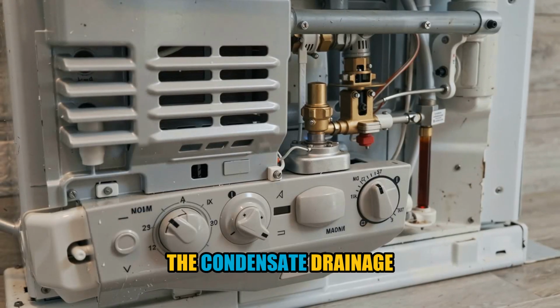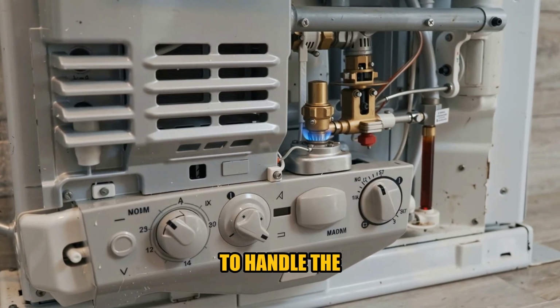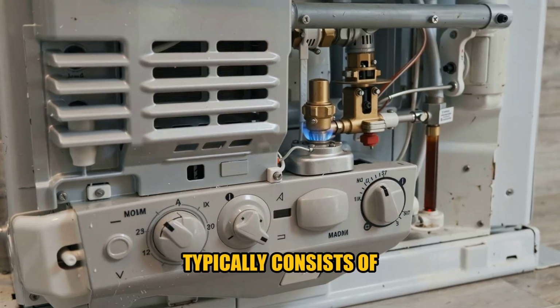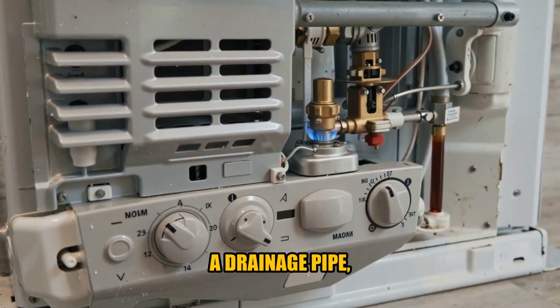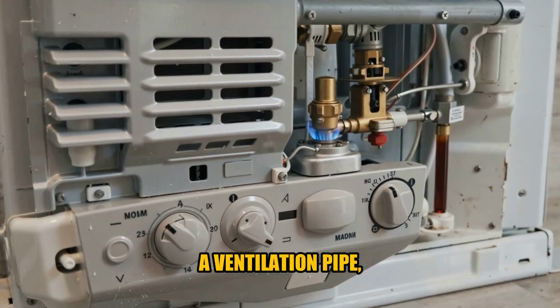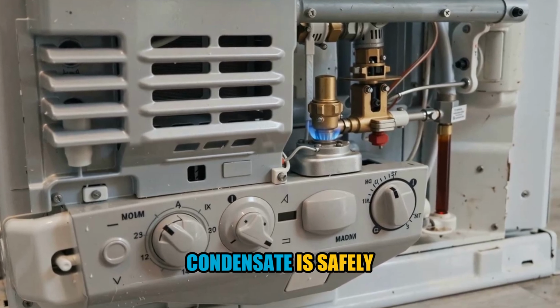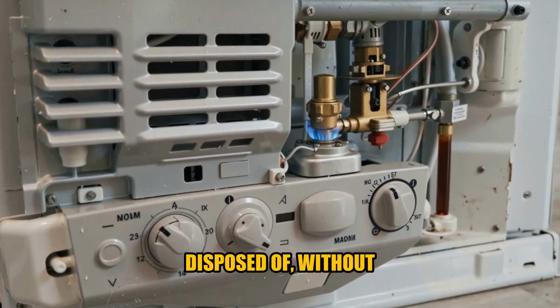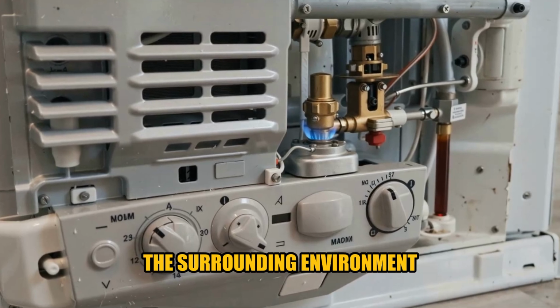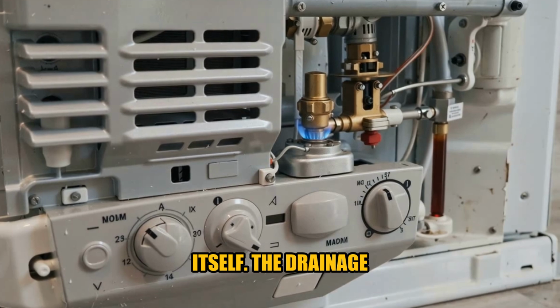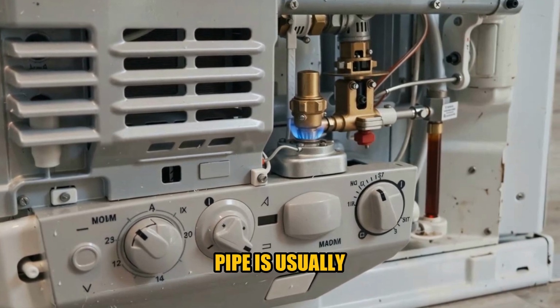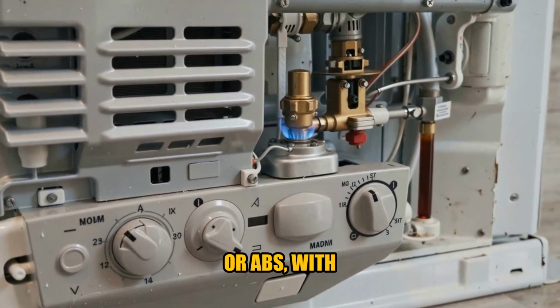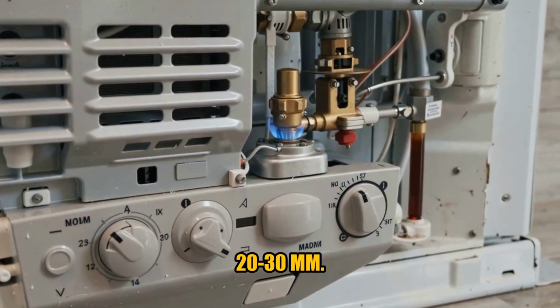The condensate drainage system is designed to handle the acidic condensate. It typically consists of a drainage pipe, a trap, and a ventilation pipe, ensuring that the condensate is safely disposed of without causing damage to the surrounding environment or the boiler itself. The drainage pipe is usually made of PVC or ABS with a diameter of 20-30 millimeters.